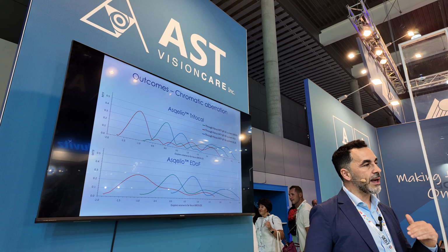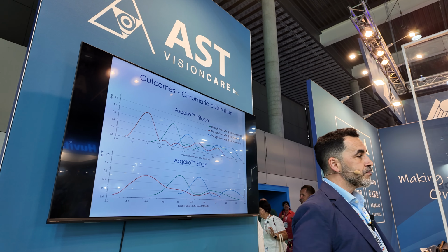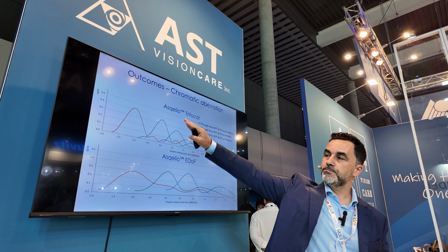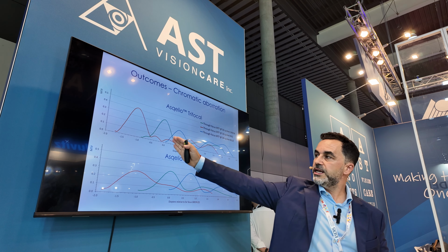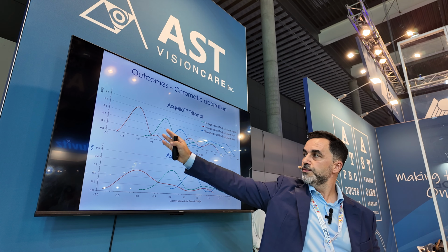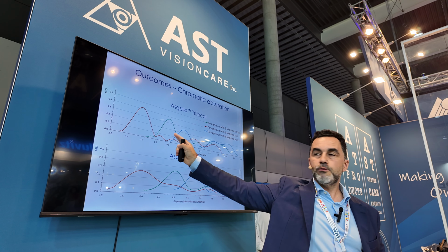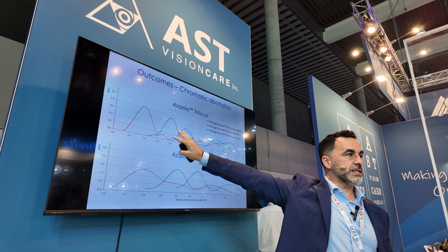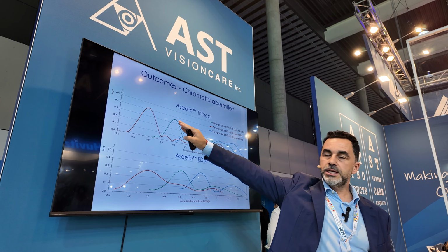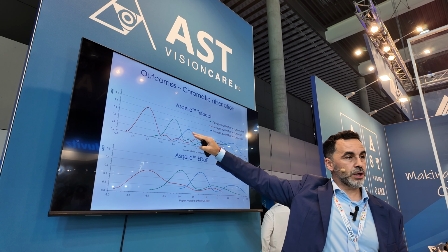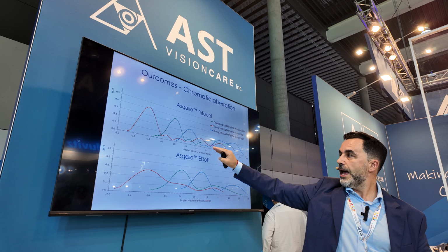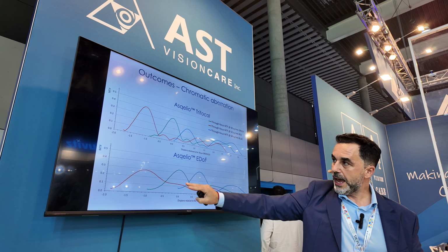But now if we look at the premium designs of these lenses, the through focus for each of the wavelengths, we see the MTF through focus that is centered on the green, as we normally do. So we can see the shift between green, blue, and red. And we can see that the distance for the trifocal design is optimized for the red, slightly decreased for the green and blue, and that shifts over for the near vision as well. And the opposite happens with the EDOF design.